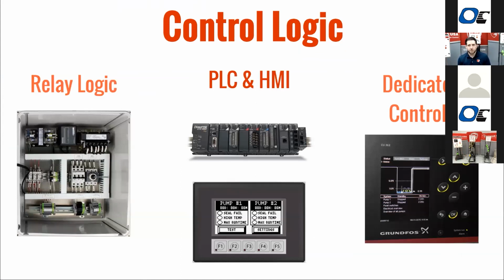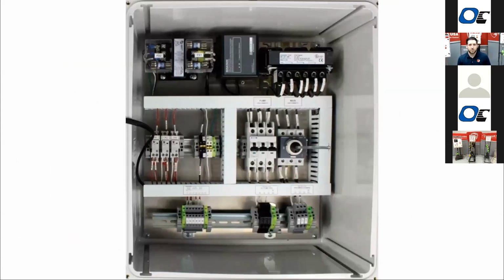Okay. So really 3 different types of ways that we would design our control panels. We're kind of starting from good, better, best in terms of the amount of control and features that you get. So the first one here is a relay logic control panel, meaning it is using these control relays here to get feedback from the float switches and turn your pumps on and off, things like that. So it's a very simple control system, all mechanical. There's no PLC or touchscreen, no electronics in there, no programming.